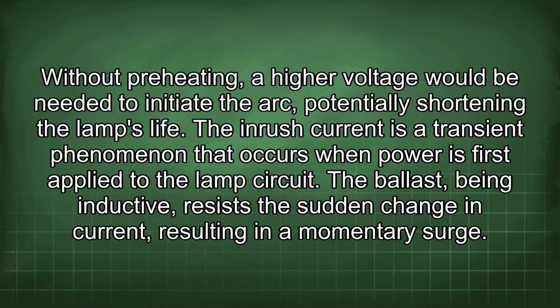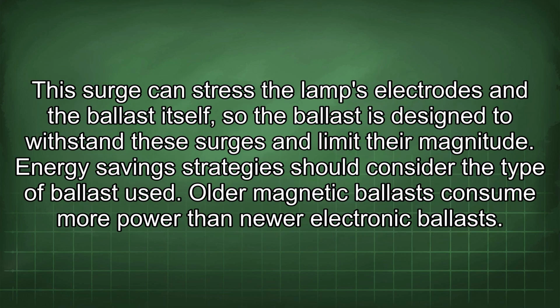The inrush current is a transient phenomenon that occurs when power is first applied to the lamp circuit. The ballast, being inductive, resists the sudden change in current, resulting in a momentary surge. This surge can stress the lamp's electrodes and the ballast itself, so the ballast is designed to withstand these surges and limit their magnitude. Energy-saving strategies should consider the type of ballast used.